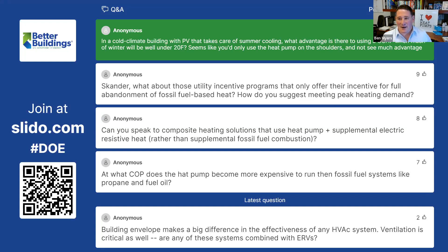But I think it's incorrect to assume heat pumps won't operate under 20 degrees Fahrenheit. We think they'll operate well under 20 degrees, into negative degree territory, without issues based on what we've seen recently. This is something owners need to prove out with more data to dispel these concerns. I saw a report out of Maine - homeowners there are very happy with their heat pump performance in cold weather, sub-zero temperatures. We need to do a better job getting that word out on heat pumps.